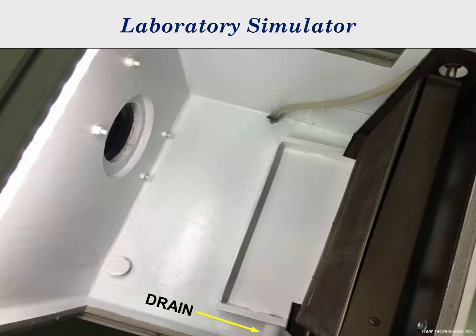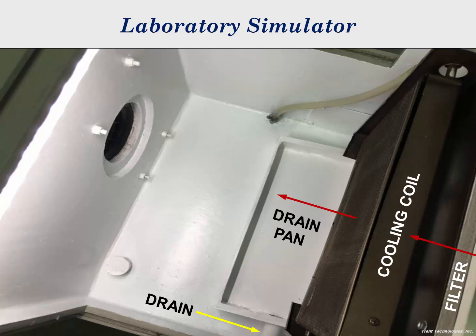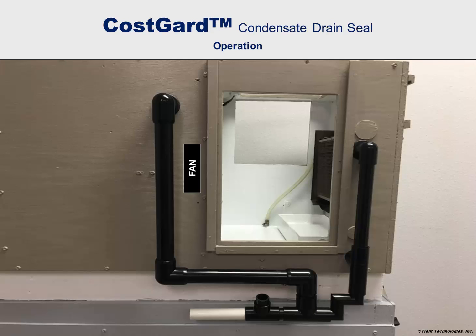Just as in a real system, air is drawn through the filter, the cooling coil, across the drain pan, and into the fan. The CostGard condensate drain seal installed on this simulated air handler helps explain how the device functions. A small quantity of air is taken from the positive pressure side of the fan. A portion of this air is discharged through the condensate drain pipe to ensure that outside air and pollutants are not drawn into the system.